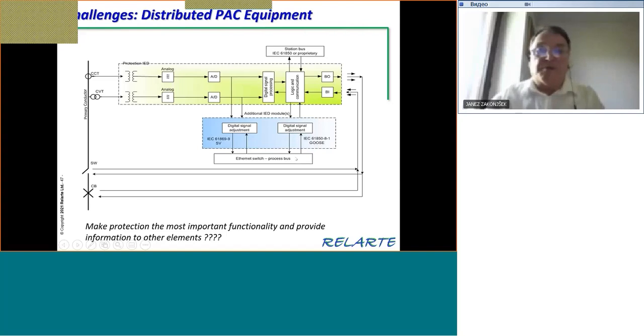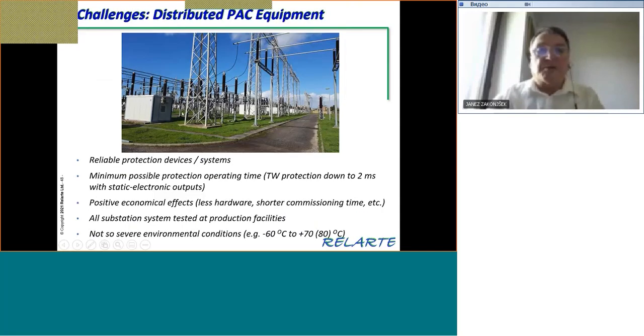And if you look at this picture, then we can look into busbar protection. They called it distributed busbar protection, although this is under question if it is correct expression. But that was when the relays were used like this, and they were sending digital signals, for example, sampled values, to the central unit for busbar protection, and then it has operated back into here. And at the same time, they were able to use here also another protection as backup protection in such systems.